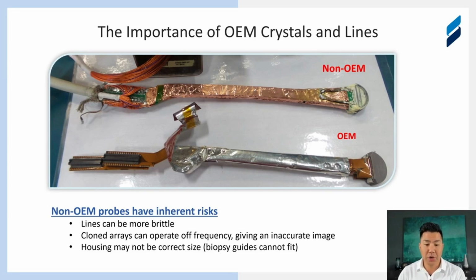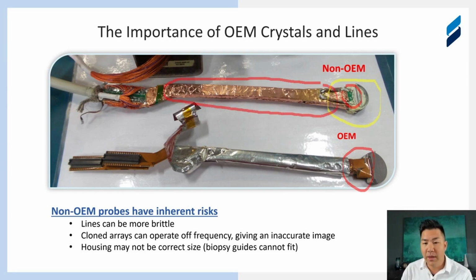Now, as we can see in the picture that we have, the non-OEM on top, you can see just the build quality, and we can start from the right here. The crystal just isn't constructed in the same way. It is a hard PCB, and I will mark the hard PCB here, relative to the OEM down below. It's all flex circuits to allow for some maneuverability and some less rigidity, and by the design they just last longer with these specific transvaginal probes that we're looking at. You can see that the shielding on the non-OEM is just basic copper tape, and then you have the grounding from the crystal soldered to the copper tape.